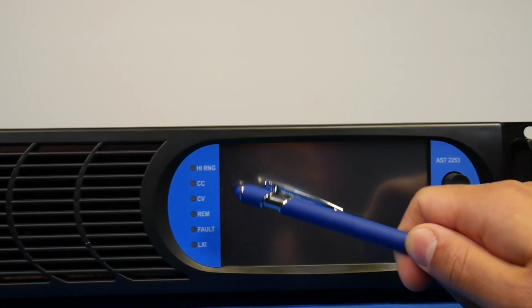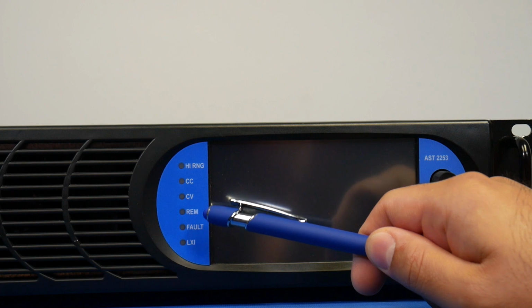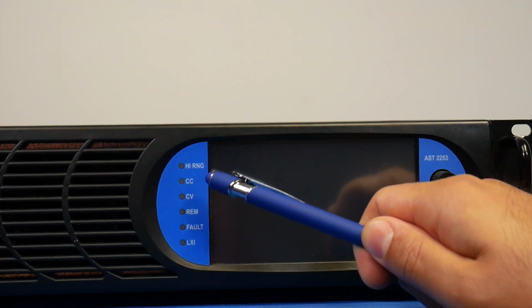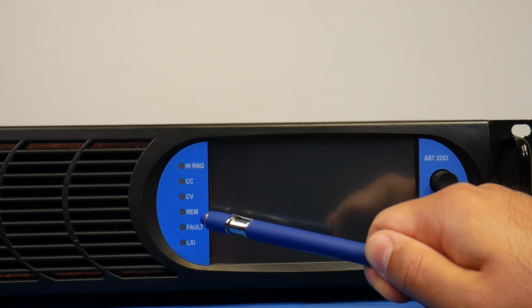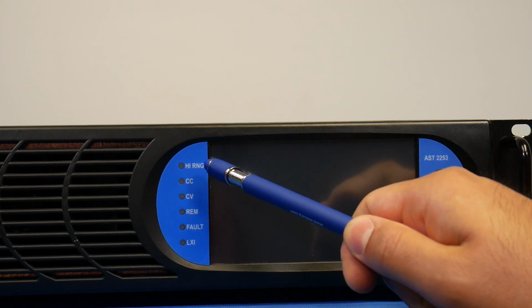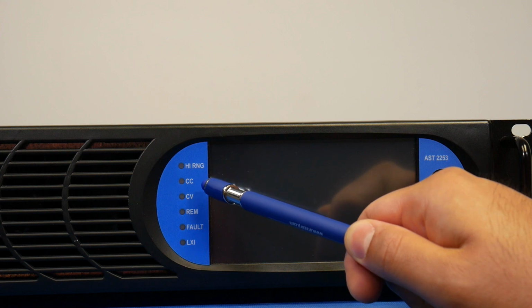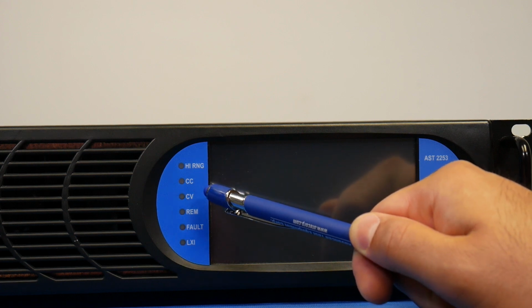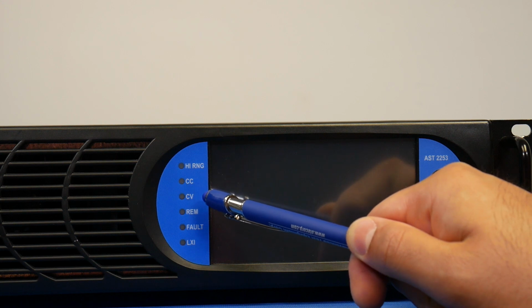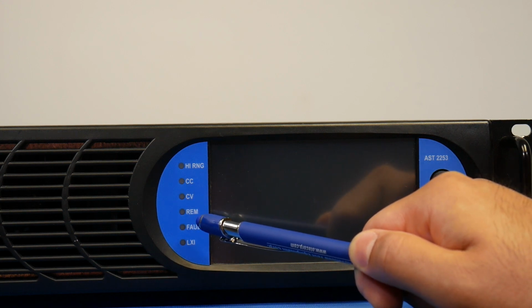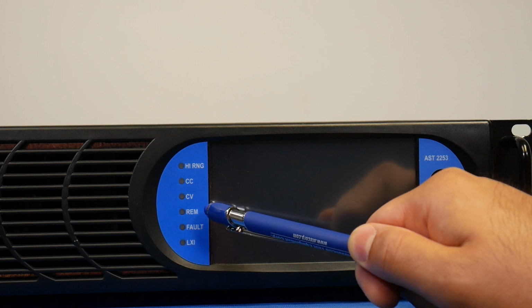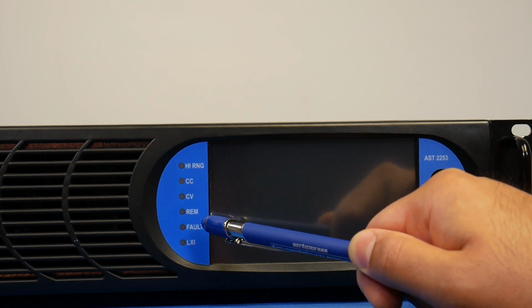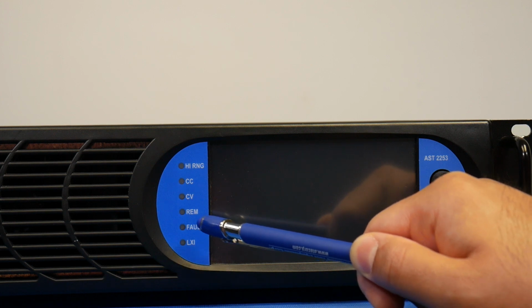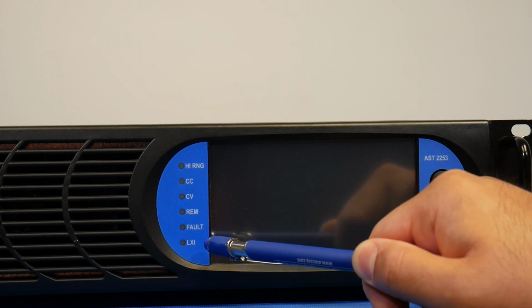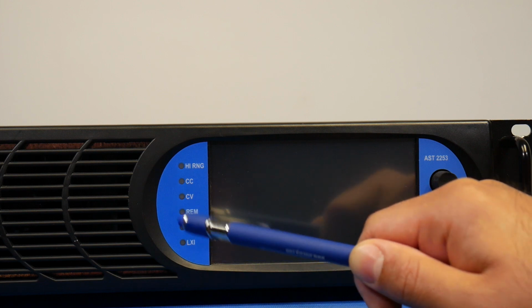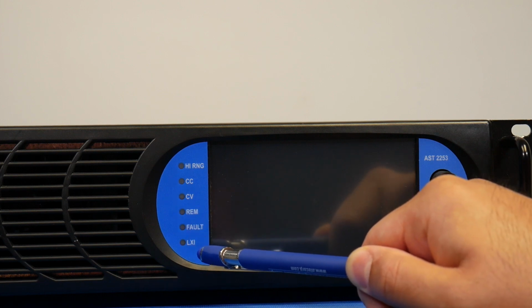Afterwards, we are going to go over the light indicators of the Asterion device. Whenever we are conducting high voltage tests, the high range light will be turned on. Whenever we're conducting constant current and constant voltage tests, these lights will turn on. Whenever we are controlling the device remotely, the remote light will turn on, or whenever there is a fault on the test, the fault light will turn on. Lastly, whenever the LXI is activated, the LXI light will turn on.